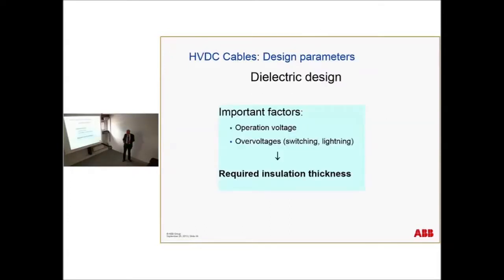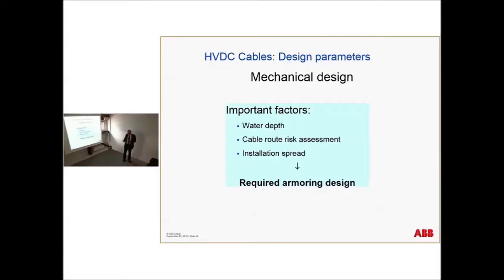For the electrical withstand, we have to look into the operation voltage and also the overvoltages that might occur during switching of the cable, and it can also be subjected to lightning strokes. This will give a thickness of the insulation, also quite obvious. Mechanical design is also about the water depth. The cable must be strong enough to carry its own weight during installation. If you have a depth of 2,000 meters and a cable that weighs 100 kilos per meter, then you can easily think that the armoring must be very strong in order to carry the weight of the cable itself during installation.